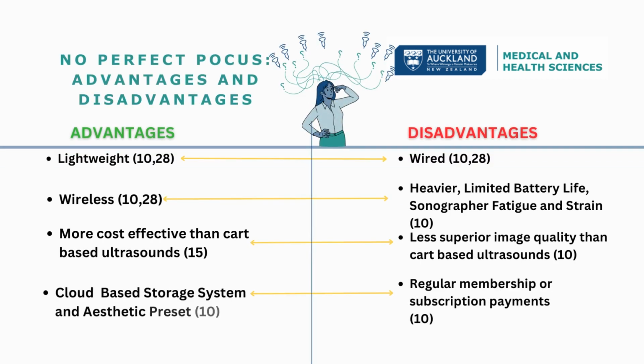There are many ultrasound devices in the market, but there is no perfect handheld POCUS, so each probe has advantages and disadvantages. The main advantages of handheld transducers are portability, user friendliness, cost effectiveness, device compatibility, aesthetic preset, and in general, high quality images. However, the disadvantages vary between transducers. Regarding portability, wireless transducers are more portable but heavier due to the batteries inside the transducer, which causes wrist fatigue for the sonographer over time. The battery is also not suitable for long scanning sessions.